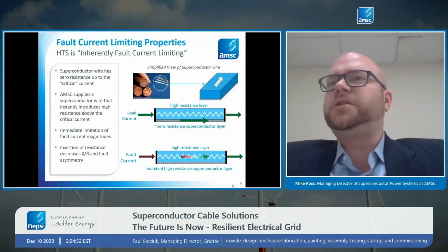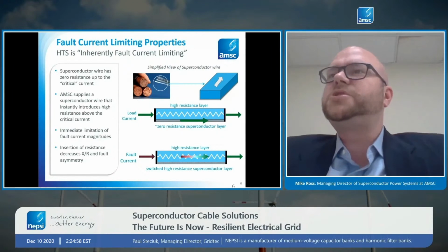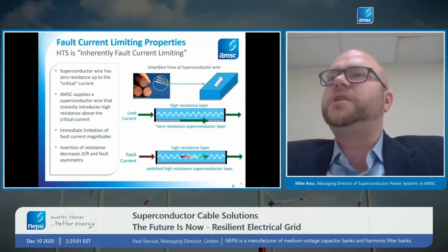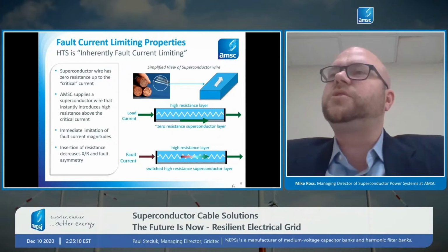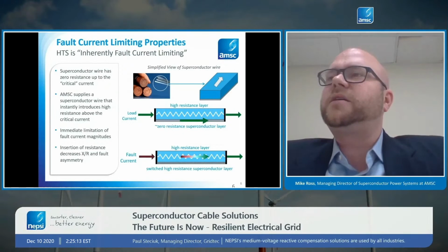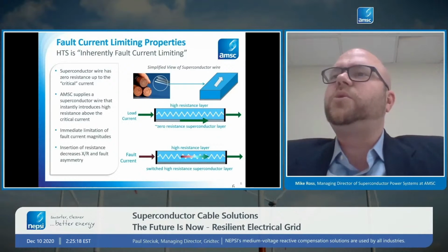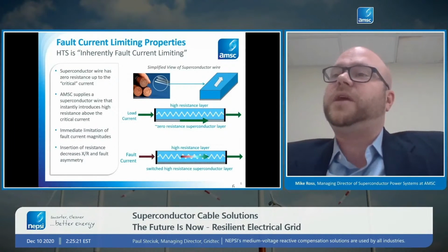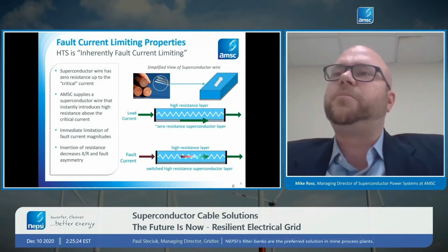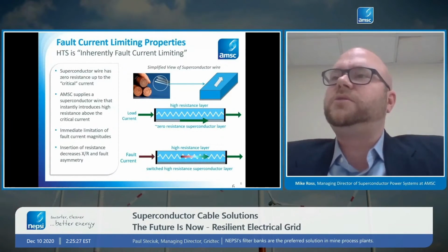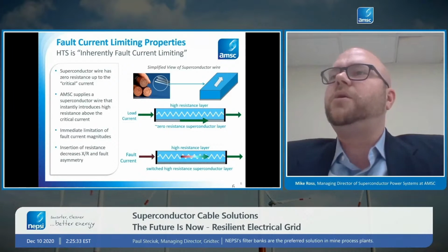Just to talk a little bit more about the fault current limiting aspects of the cables. The wire itself that I was showing you before, that can carry 200 amps in that little wire, is really only 1% superconductor material. Superconductor material is a sort of ceramic material, like a coffee cup kind of material. So it's breakable, it's delicate. So we had the same challenge that the fiber optic industry had. How do you take a material that's inherently brittle, like glass, and turn it into a cable that can be bent and pulled and twisted and buried underground for 40 years without damage?